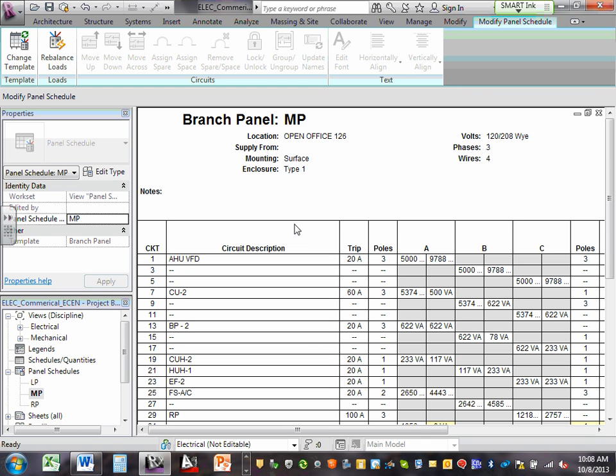Here's my panel — I set the voltage, everything is good, now I'm going to circuit. All of a sudden it doesn't allow you to circuit. Well, you put 30 circuits in it, and now you're up to 31 — how are you going to put 31 circuits in a 30-circuit panel? Revit is intelligent enough — in CAD it doesn't care, but Revit will tell you: you're trying to circuit a 31st circuit into a 30-circuit panel. You need to go back to your panel, make it 40, and then circuit again.